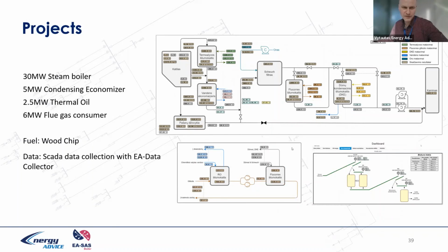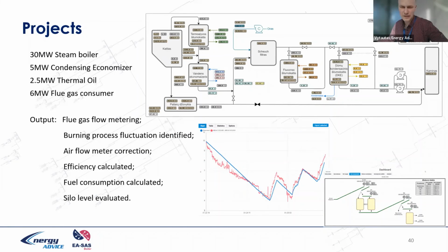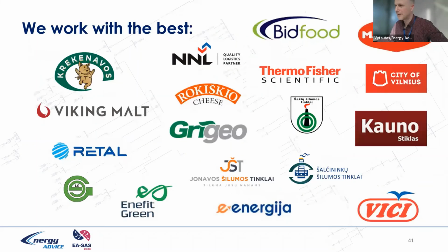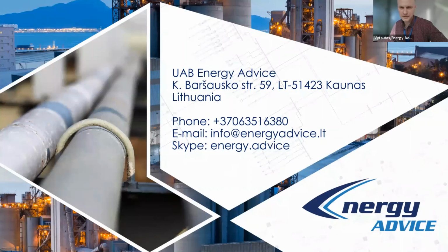A 30 megawatt steam boiler with a 5 megawatt condensing economizer, thermal oil, and a gas consumer. It's quite a sophisticated project, with many components, as you can see here, and also fuel stored in a silo. For the client, it was important to account for the fuel. You can see the silo level in red and how we account for it in blue. It's a little bit of metering error, but finally it tracks quite well.